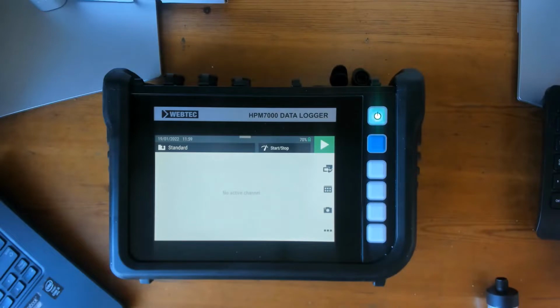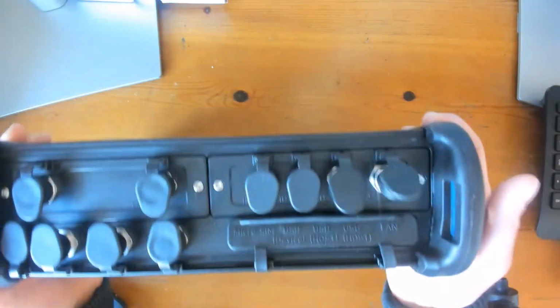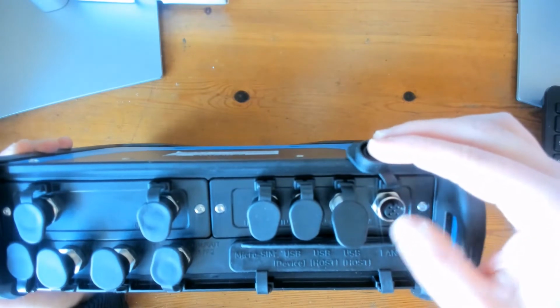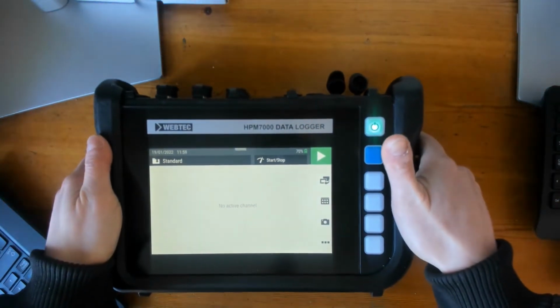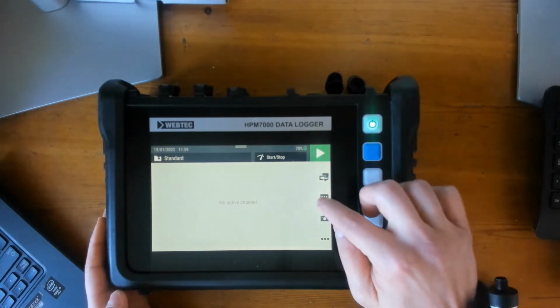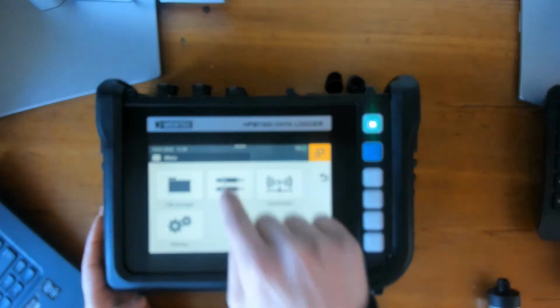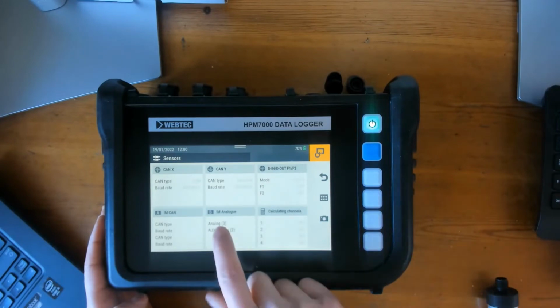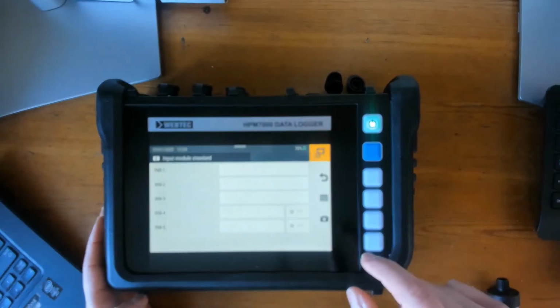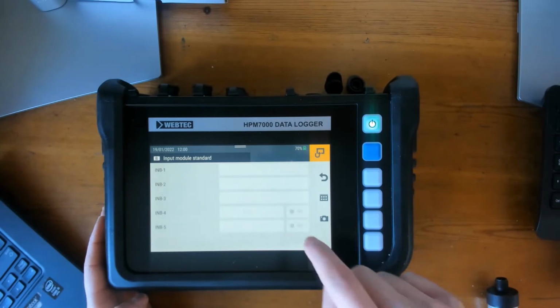So to connect a 4 to 20 milliamp sensor to the HPM7000, we will need the analog input module, and we will be using the M12 connector here. So to configure the sensor, we'll go to the menu, Sensors, Input Module Analog, and I will be connecting the sensor to input 4.